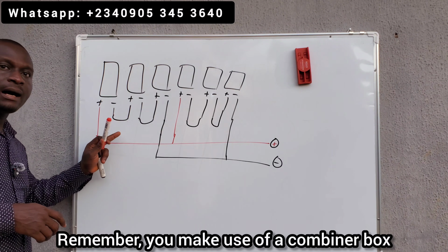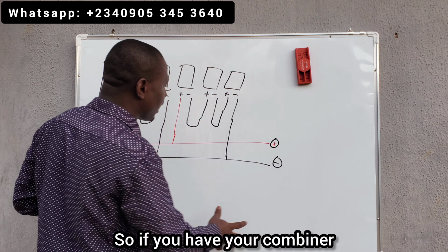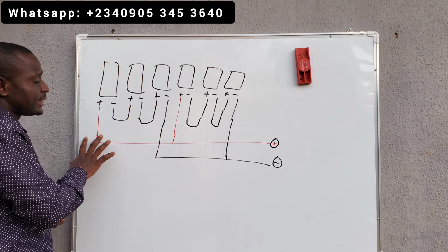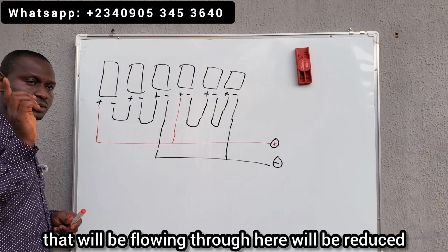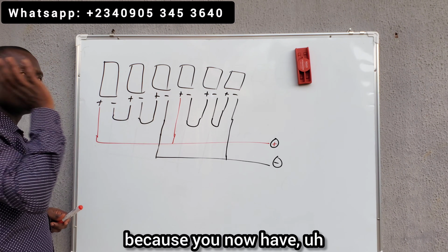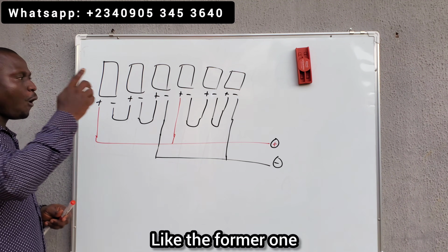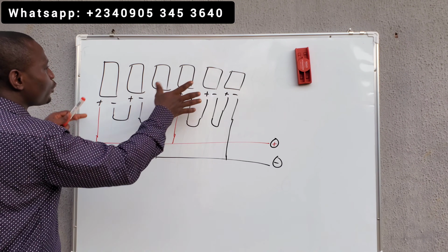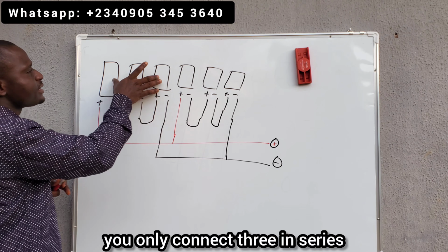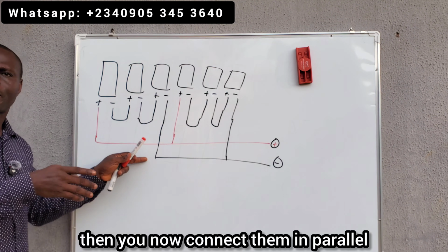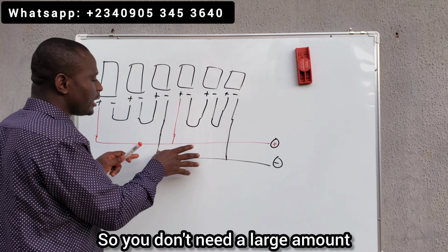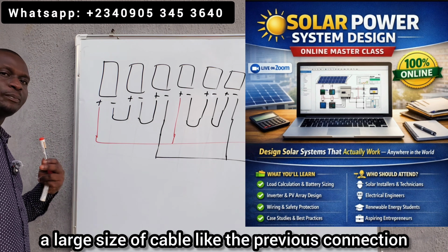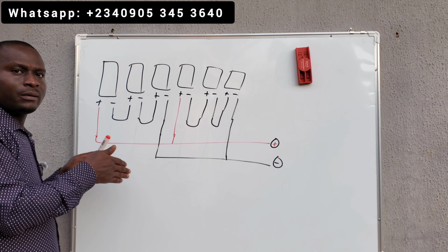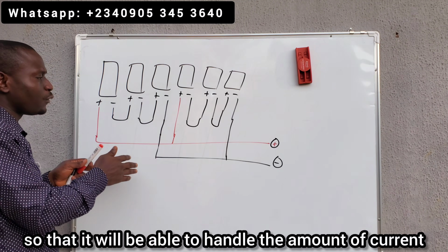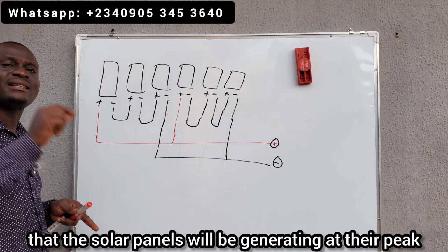Remember, you make use of a combiner box. So with your combiner, you can see that the amount of current flowing through here will be reduced because you now have two parallel connections. Like the former one, all 6 panels were connected in parallel, but with this MPPT charge controller, you only connect 3 in series, then connect them in parallel. So you don't need as large a cable as the previous connection, but you still need to properly size your cable so it can handle the amount of current the solar panels will generate at their peak.